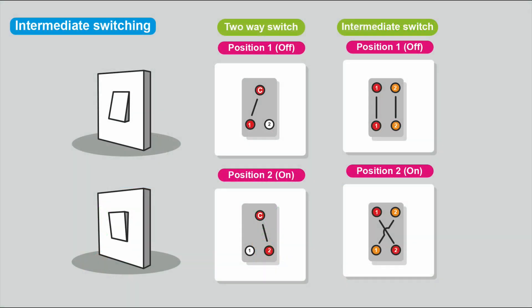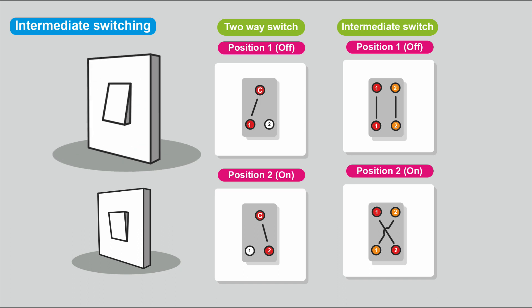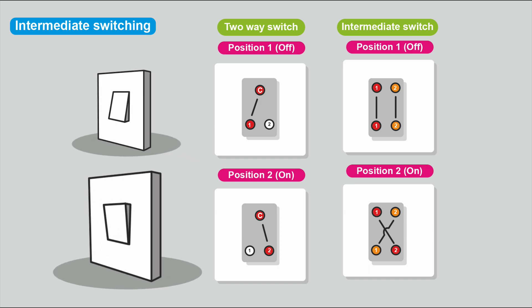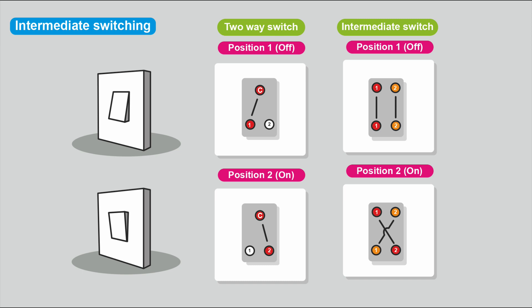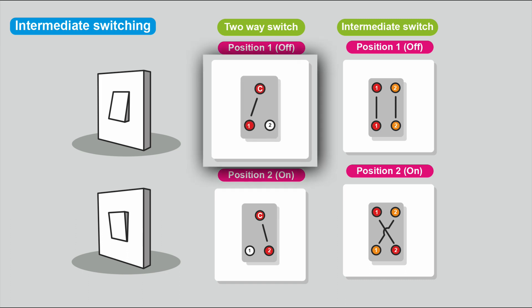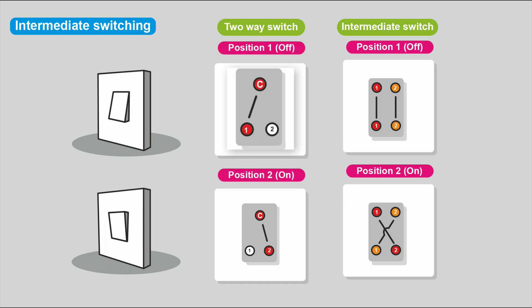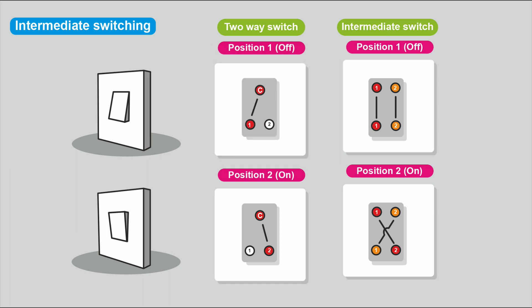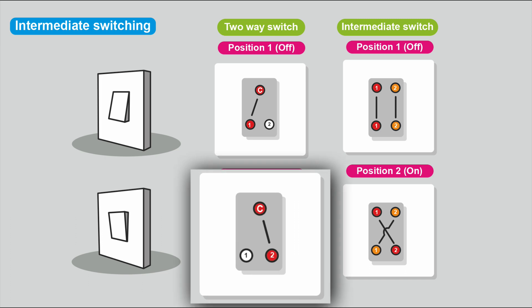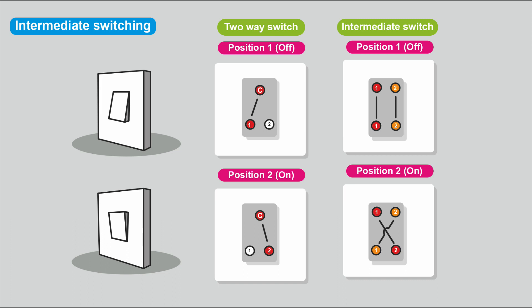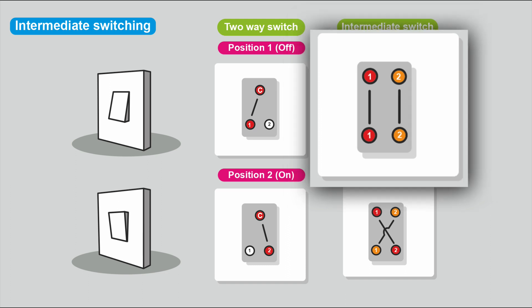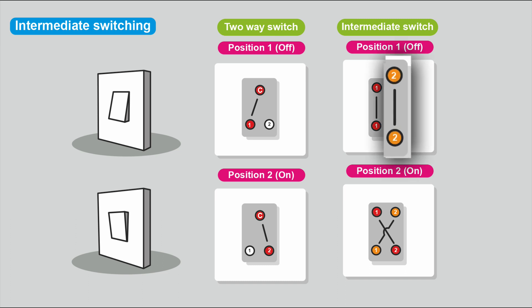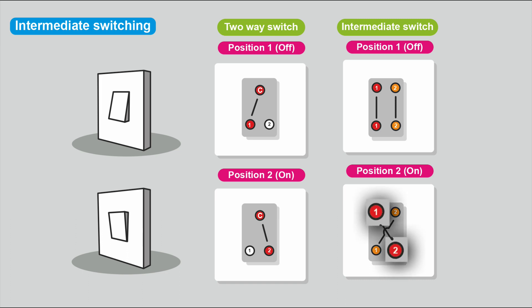These are the two-way switches and intermediate switches we'll be using. When the switch is in the off position and flicked over, it'll be on. When all switches are in the off position the light should be off; when all are on, the light should be on. In the off position, power goes from common to L1. When switched on, power goes from common to L2. The intermediate switch in position one goes one-to-one and two-to-two; in position two it's crossed over, going one-to-two and two-to-one.